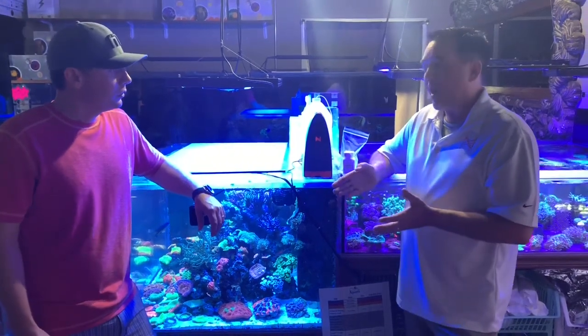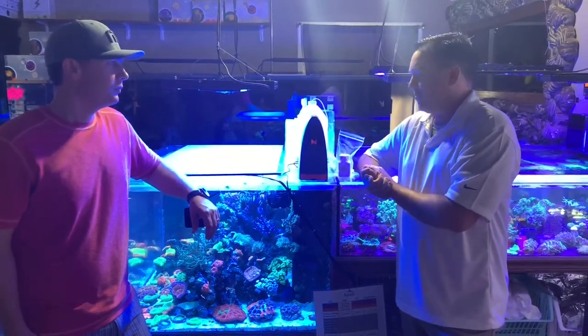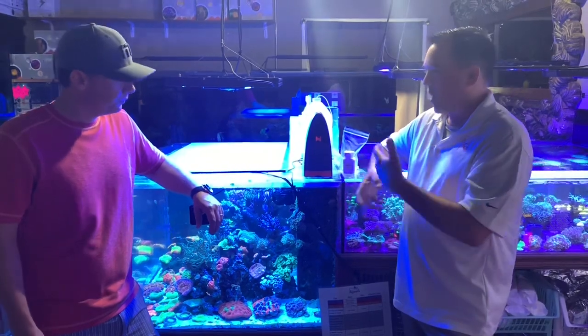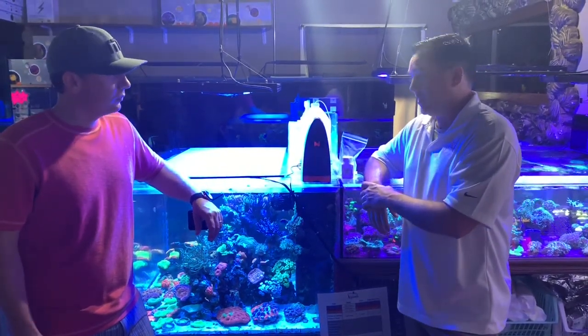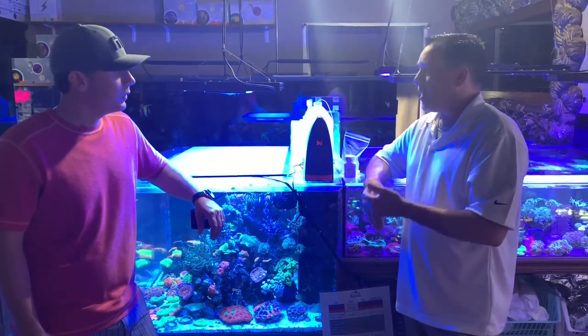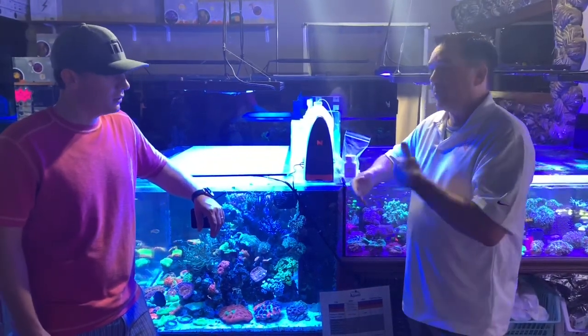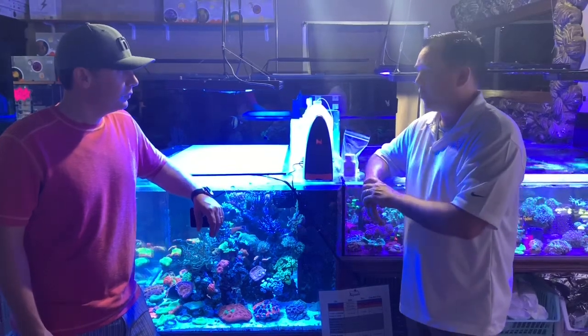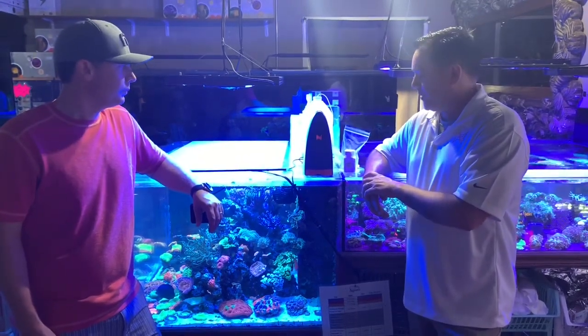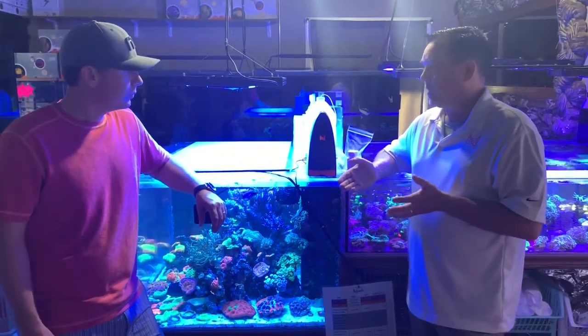This is literally a scientific piece of equipment, and all pieces of equipment that work to give you automated results require some level of calibration and maintenance. The Trident is no different. However, it does not require you to send it in — that is an option we will have. We will also have a do-it-yourself kit available for less than a hundred dollars. It'll be between $150 and $200 to send it in. We're going to have an advanced replacement option so there won't be any downtime. Is it 18 months, 24 months, 16 months? There's a lot of variability — just like your car, the manual says you need a timing belt at 70,000 miles, but a lot of people go to 90,000 and everything's just fine.